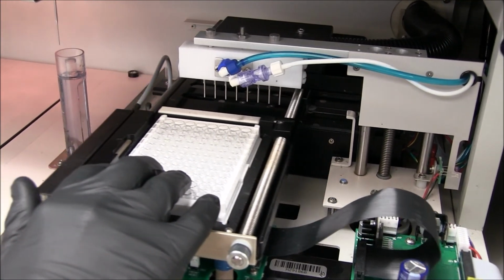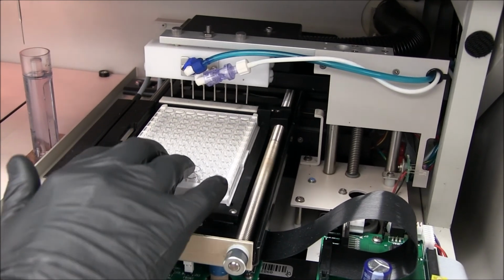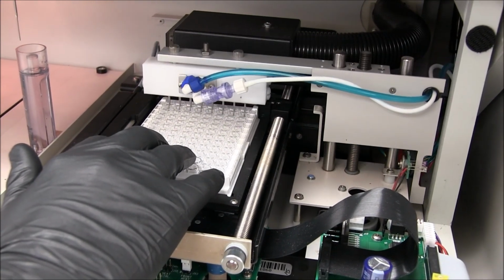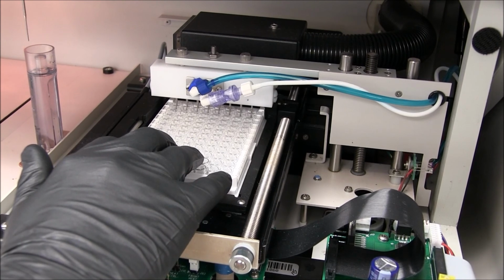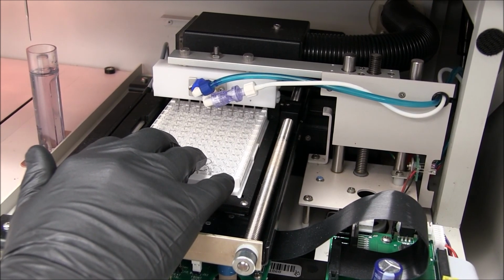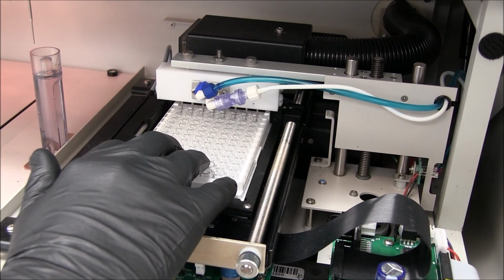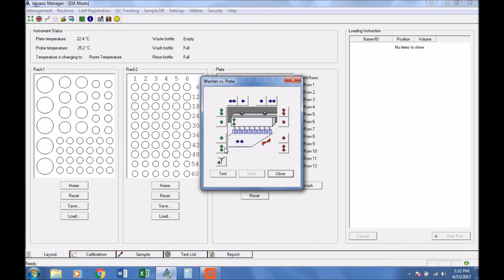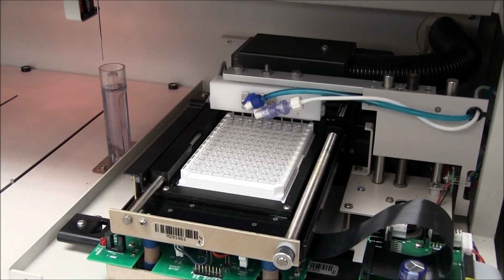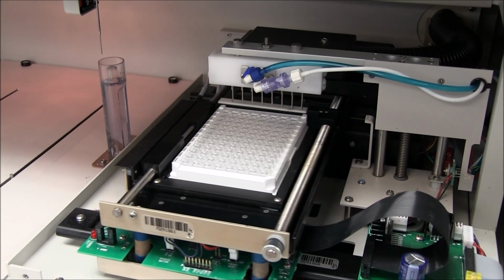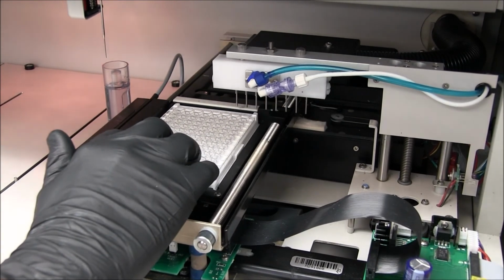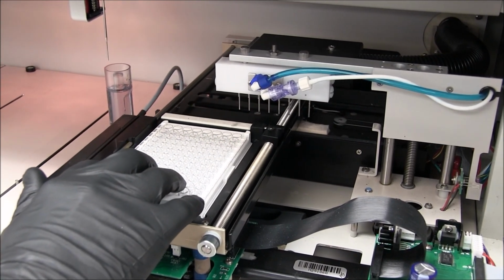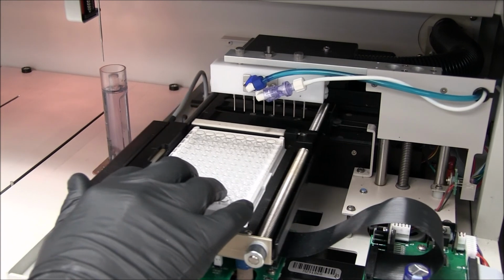In order to align the probes correctly on the z-axis top to bottom, one hand must be placed on the plate to feel for contact between the probes and the bottoms of the plate wells. It is best to click the single green up arrow until there is no contact felt, then begin to click the single green down arrow until the very first contact is felt. Then click the double green down arrow once and save these settings.